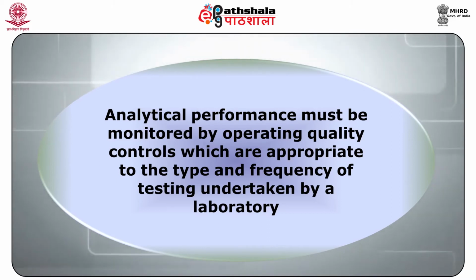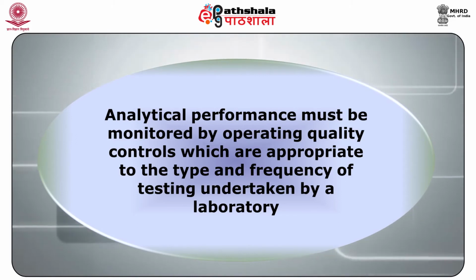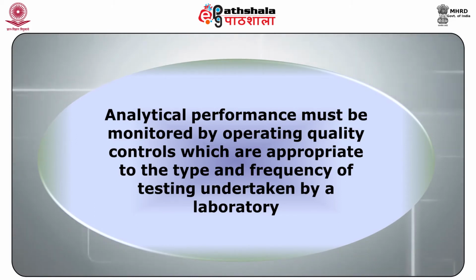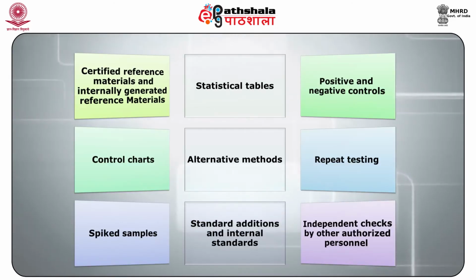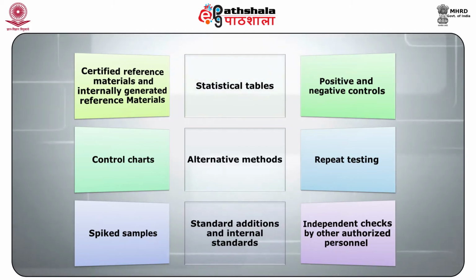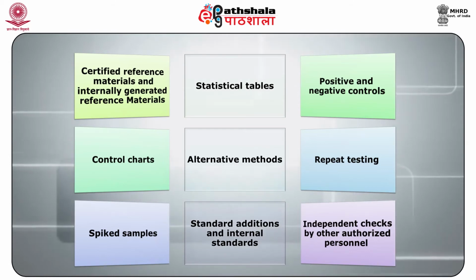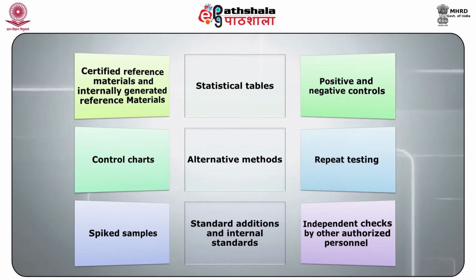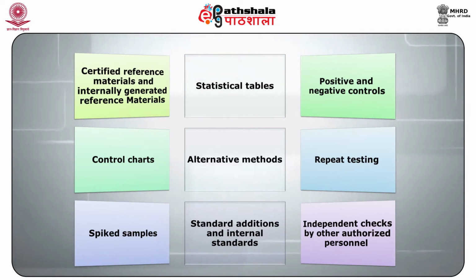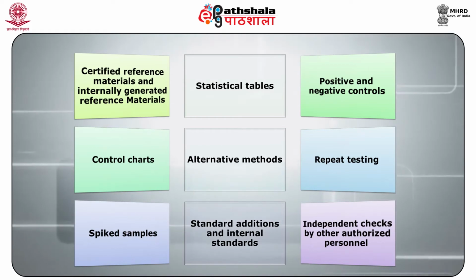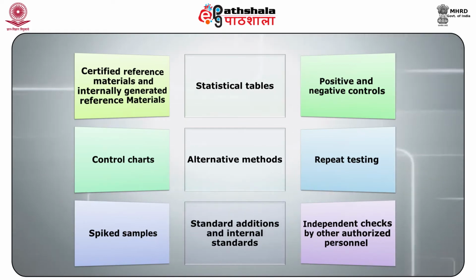The range of quality control activities available to laboratories includes the use of reference collections, certified reference materials and internally generated reference materials, statistical tables, positive and negative controls, control charts, alternative methods, repeat testing, spiked samples, standard additions and internal standards, independent checks, verification by authorized personnel.